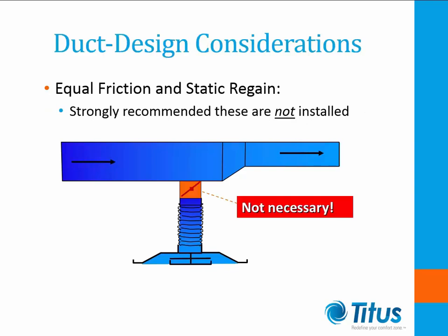When used as a standalone modulator, traditional static regain design rules apply. The static regain ductwork design method has been the choice of engineers for many years, even though it is more difficult and time-consuming than the equal friction technique. Static regain designs have been attributed to yielding more balanced systems that have better flow characteristics than equal friction systems.